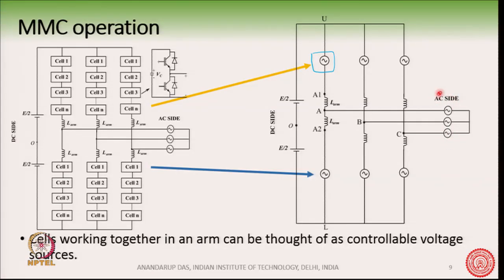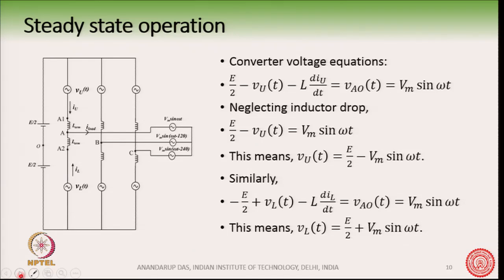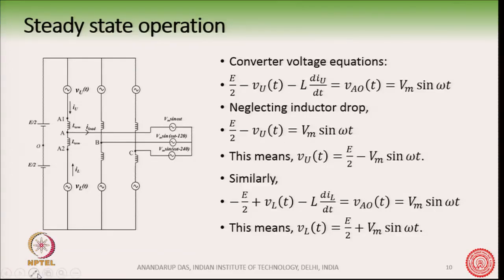This arm is now replaced by a controllable voltage source in the circuit model. There are six such controllable voltage sources — one per arm — corresponding to the six arms of the converter. These six controllable voltage sources are completely independent of each other, which is something unique to this converter. On one side we have the AC, and on the other side we have the DC.